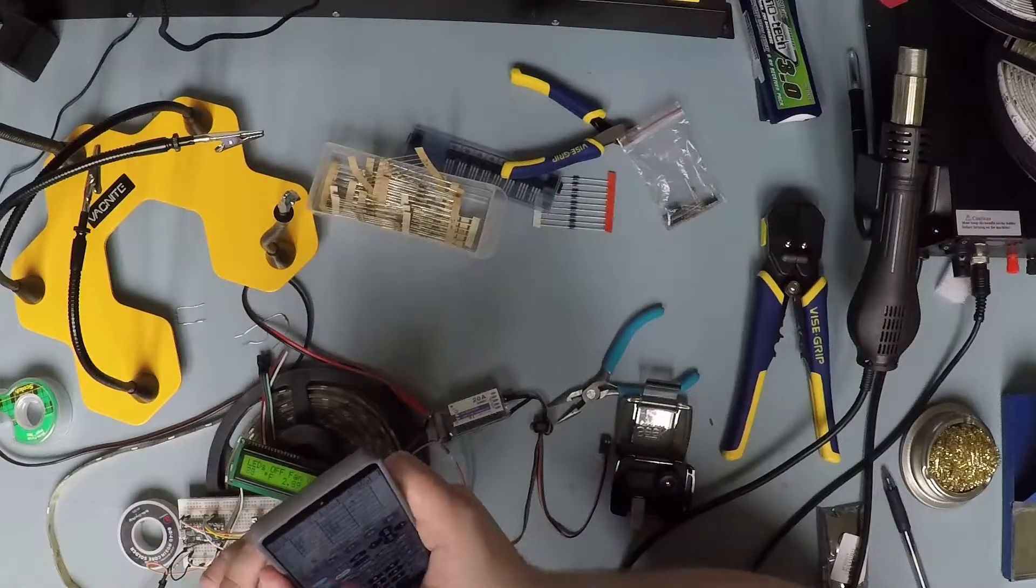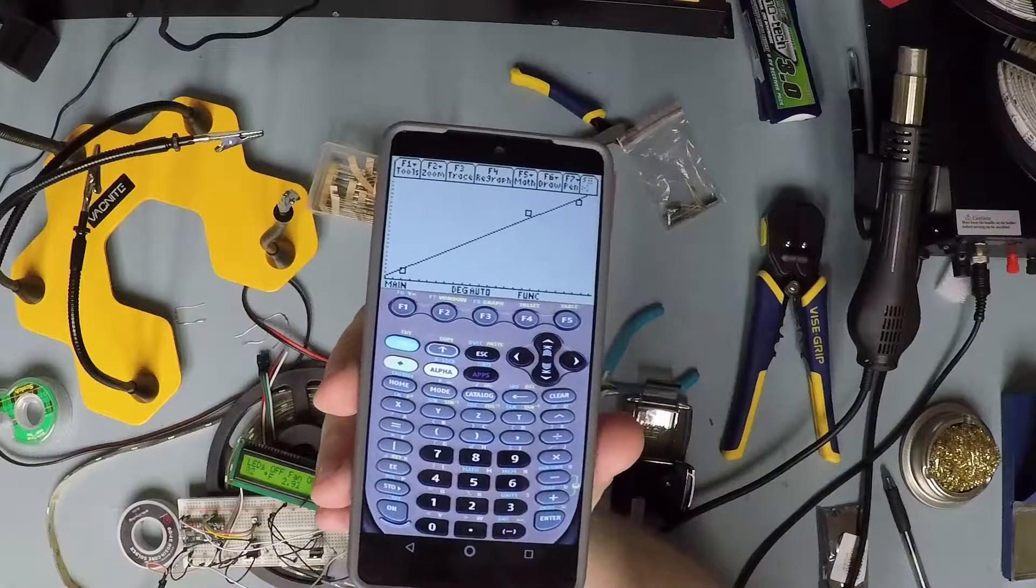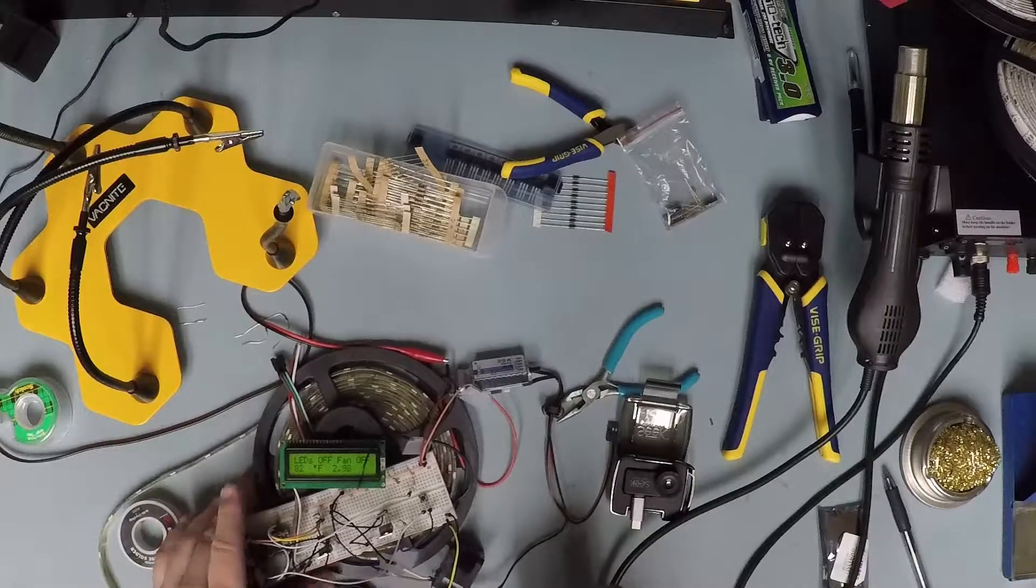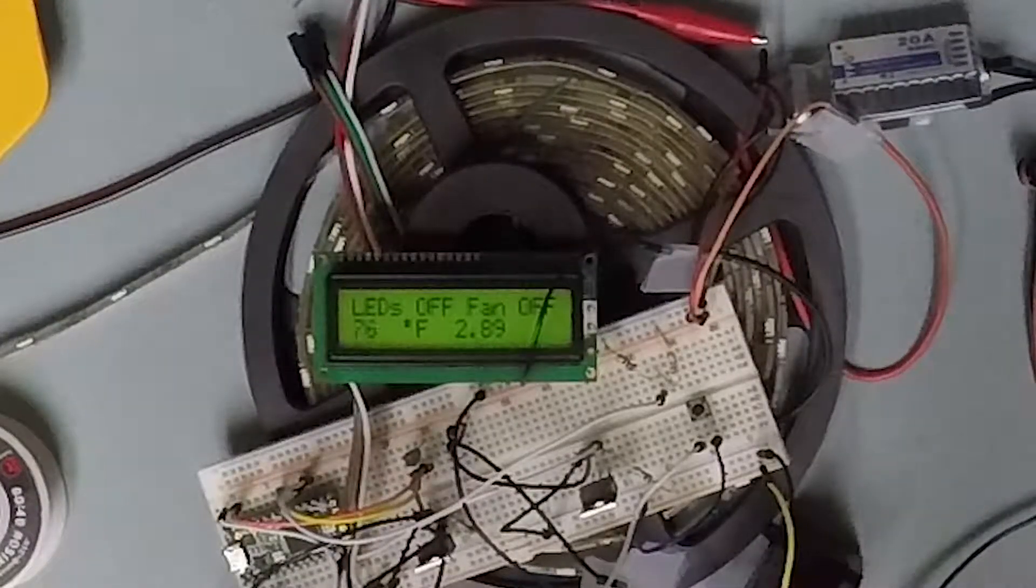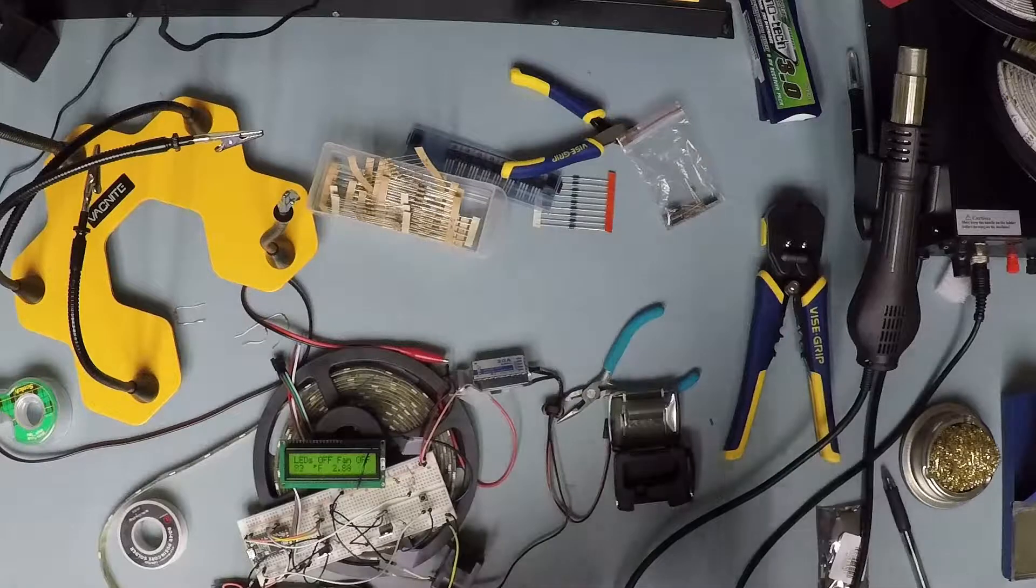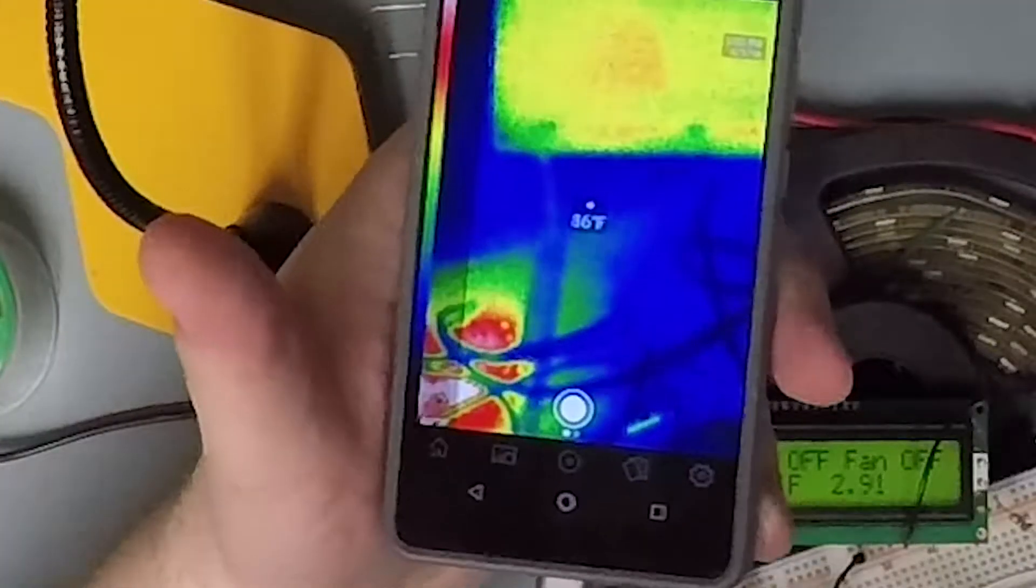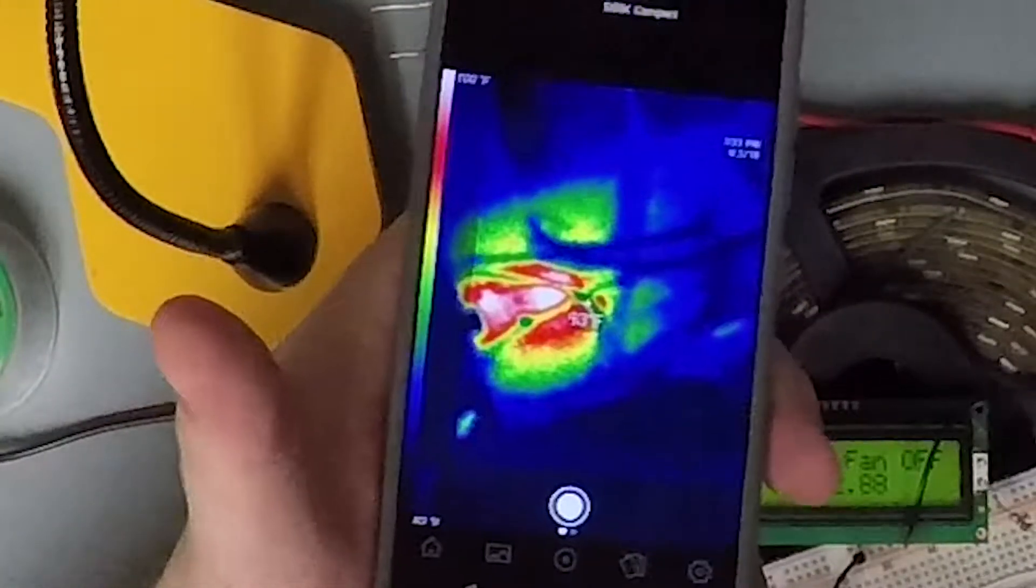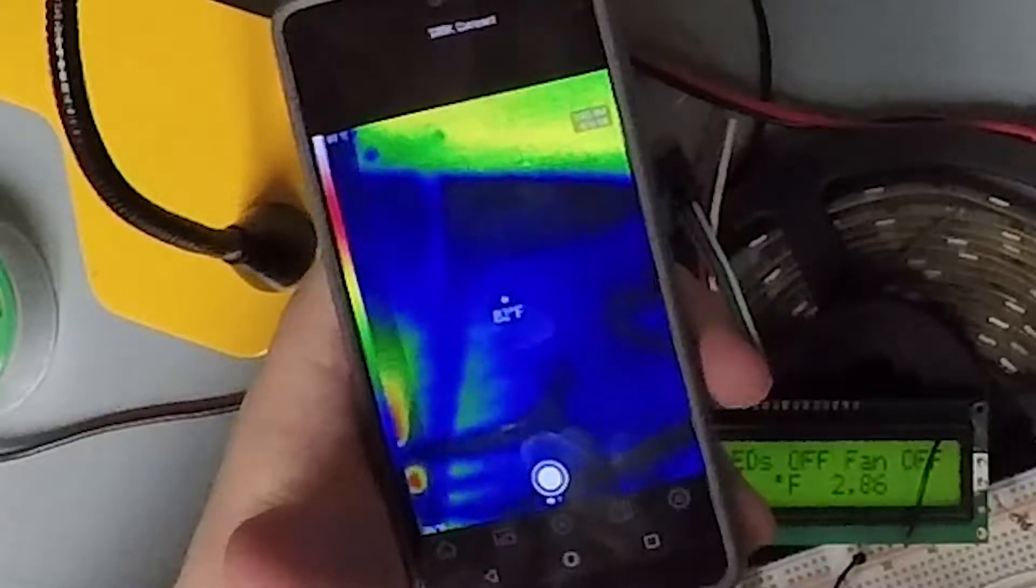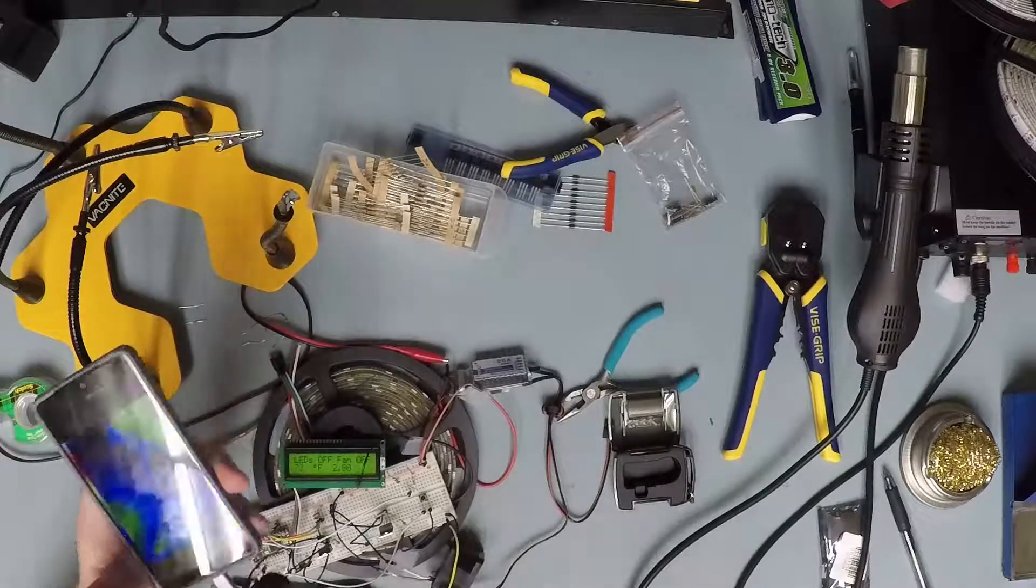So if we go into our graph here, if I hit the button right, you can see my three data points and the projected line I have on there. And having put that data in, my display is now calling somewhere in the 80 to 81 degree range right here, which means if I plug in the old camera. So yeah it's calling about 81-82 degrees. And that is what my display is also reading so I think we got her calibrated.